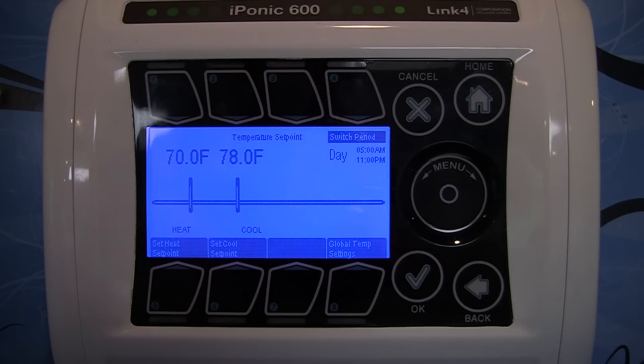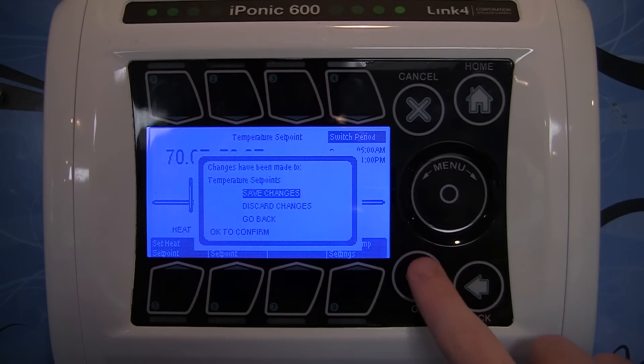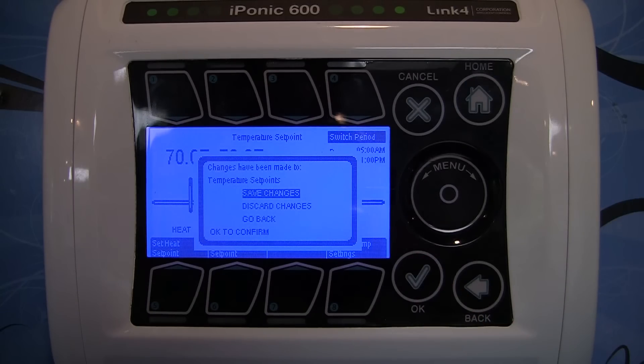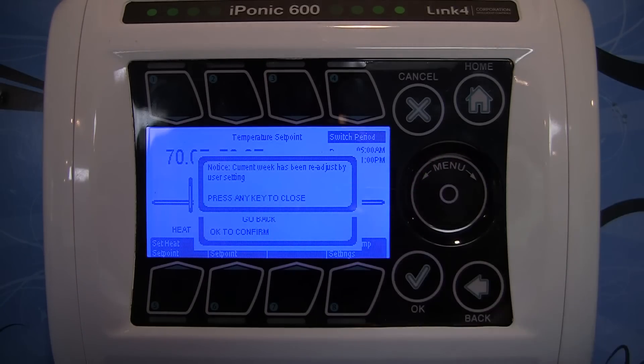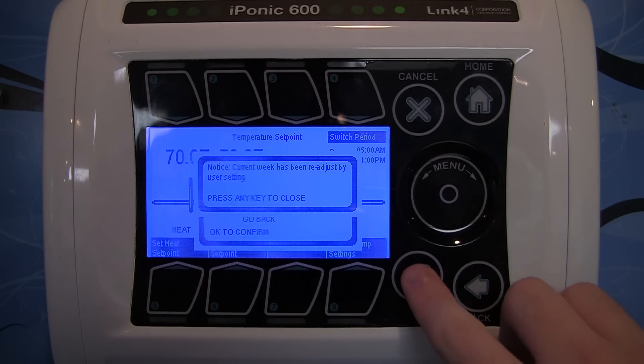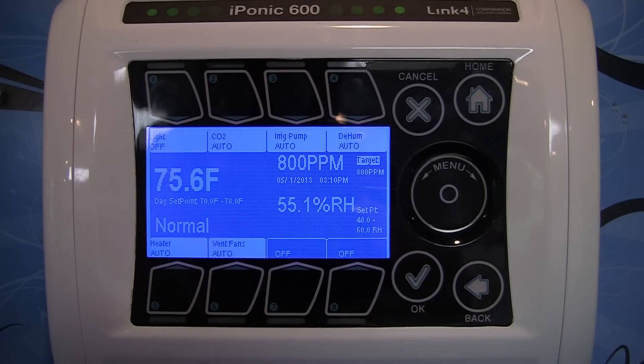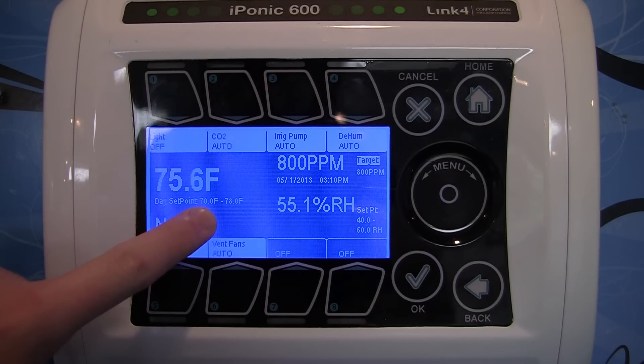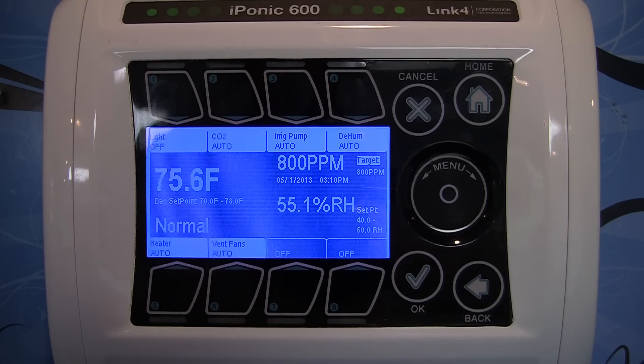When you're done setting up your set points — with your day and night set points in place — hit the home button and select save changes. It'll display a notice that the current week has been readjusted by the user setting; hit OK since we did it intentionally. You can now see that the day set point has changed to 70–78 degrees, and the current reading is 75.6.